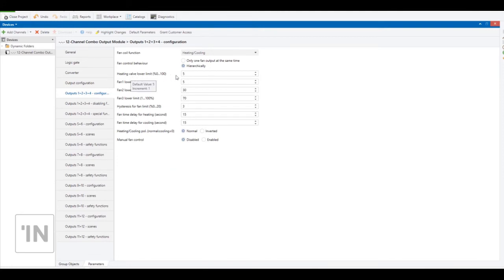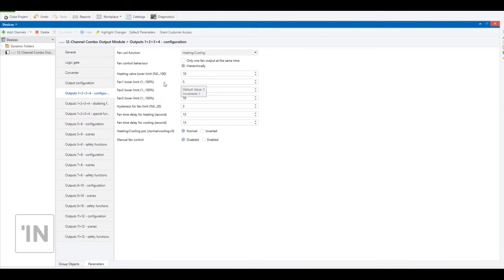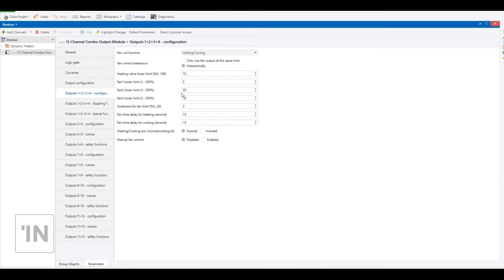Heating valve lower limit: when you send a percentage value more than, for example, five percent — or whatever value you write here — it opens the valve. If the value is not more than this, it closes the valve. You can also arrange fan lower limits in these three lines. For example, from 5% to 30% is fan level one, from 30% to 70% is fan level two, and more than 70% is fan level three.